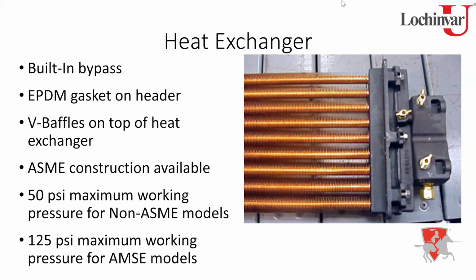So, do keep all of that in mind as you're going through here. Yeah, a couple of things about flow rates. The maximum flow rate for these heat exchangers, and it doesn't matter whether it's ASME or non-ASME, is 100 gallons per minute. And we can see the pressure ratings: 50 max for the non-ASME, and that's because of the polymer header, 125 for the ASME. But your flow rate is 100 gallons per minute maximum for all models.